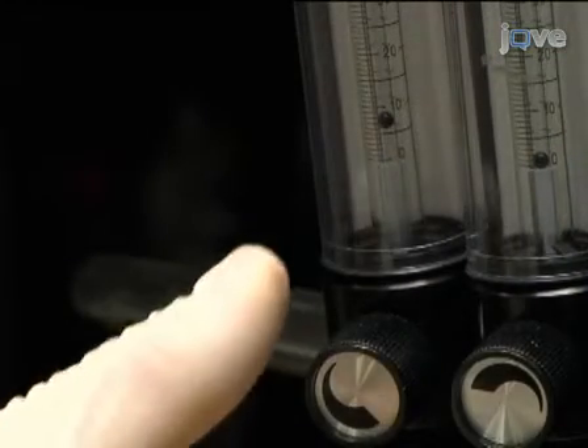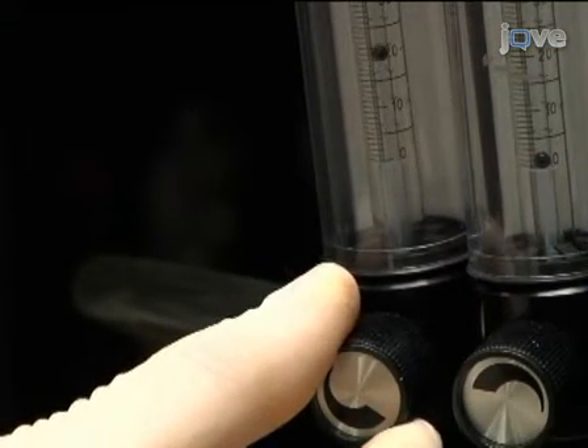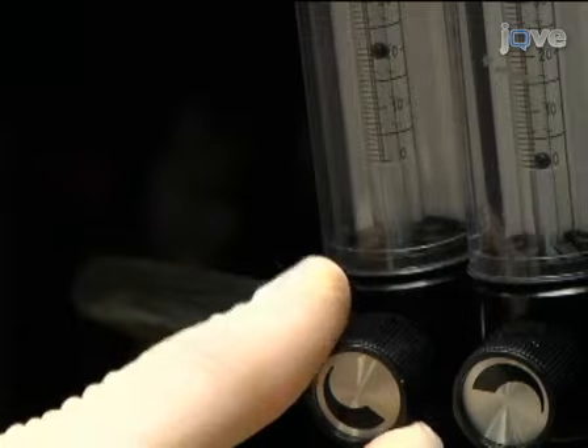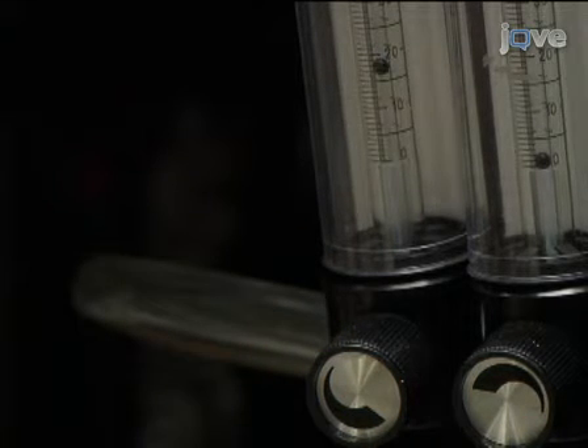Watch the flow rate value closely over the next hour and make adjustments as needed, since the pressure drop will change while the system equilibrates, altering the flow rate.